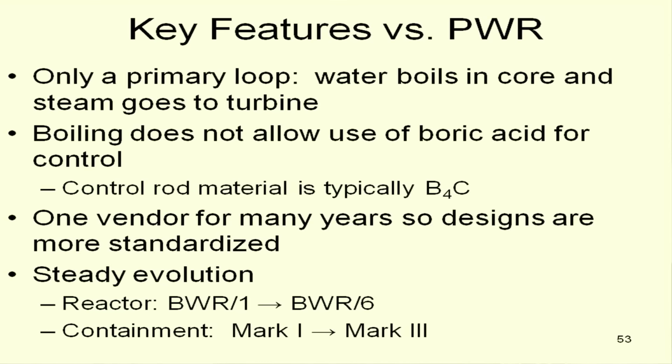And to some extent, you can control it a little bit with pumping. The control rods are boron carbide, which is a solid material. By controlling it by pumping, what I mean is if you slow down the pumping and moving the coolant through, you're still generating heat. You get more steam, which means more void space, less moderation, so power tends to drop back down. And conversely, if you pump it faster, you tend to get a little bit less void space and a little bit more moderation. So you can maneuver within that, but the control rods are it.